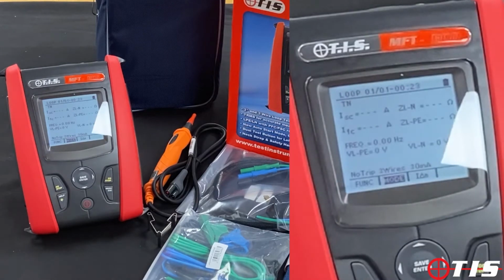Just before we move off of the loop testing side of things, in this setting, you can also dial in the different fuse or breaker characteristics which are protecting the circuit, and the unit will then give you a thumbs up or a thumbs down depending on the reading, again therefore saving potential revisits when the readings were found not to be correct when we got back to base.